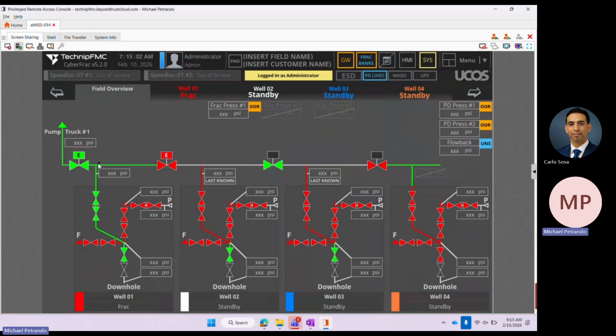However, there are situations where in this case it is reading a valve position, but it's not picking up a handle position. So they're independent of each other and they can read differently, and that can flag a user that something is wrong. Like maybe there's a blockage in your line and your handle position is closed, but your physical valve position is still open. That's a problem, right?